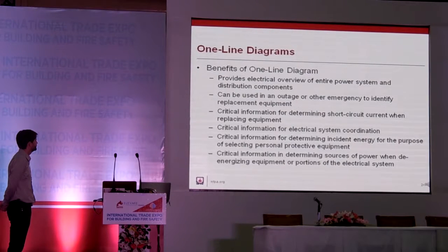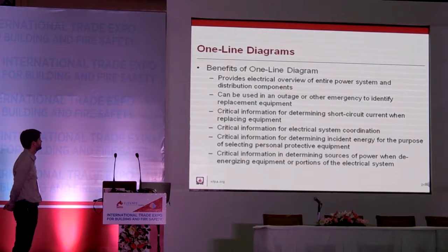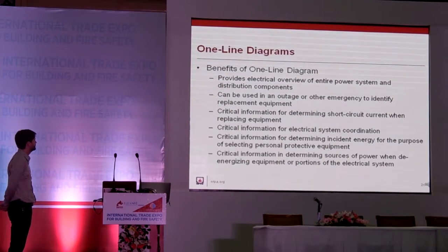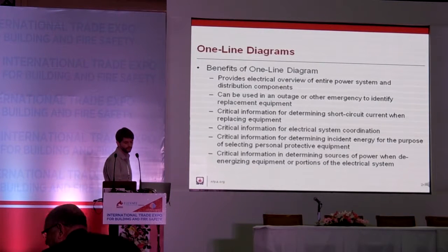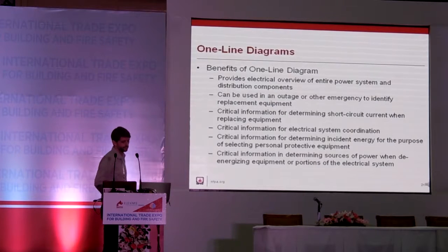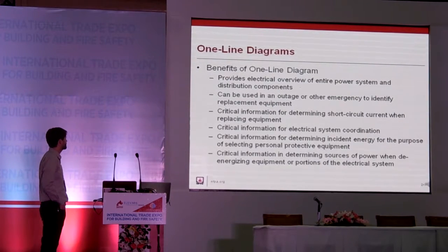Going hand in hand with that is when circuit breakers or distribution equipment is replaced, when the one-line diagram is reflective of the available fault currents within a facility, the proper interrupting ratings for protective devices, and the proper short-circuit current ratings of equipment can be ascertained. Localizing faults through the use of overcurrent protective device schemes, coordination of those overcurrent protective devices can be determined through the information contained on the one-line diagram. That's also important. The fault current and the clearing times of overcurrent protective devices are very important in establishing the incident energy values. Incident energy values are a critical piece of information that we use when selecting personal protective equipment.